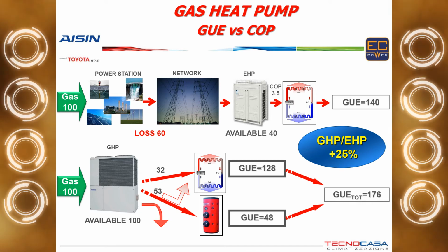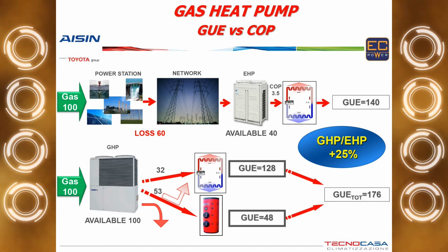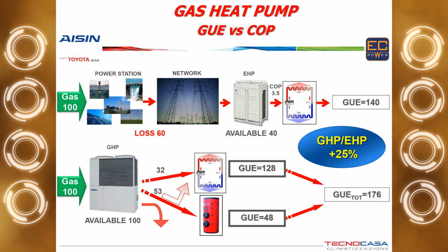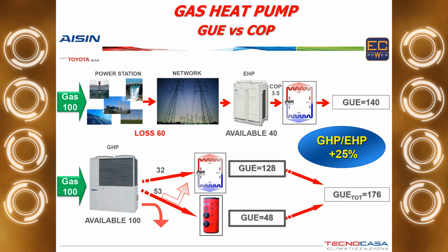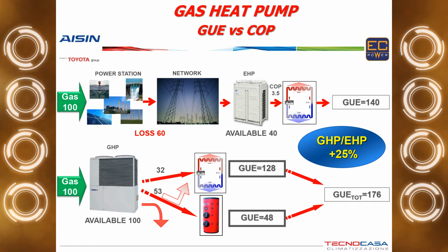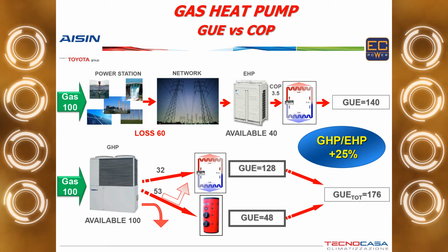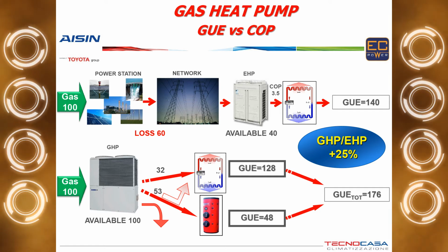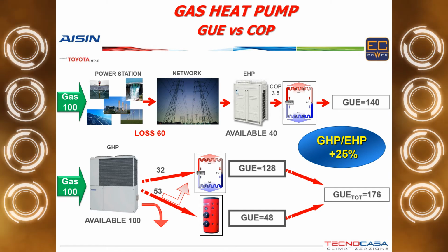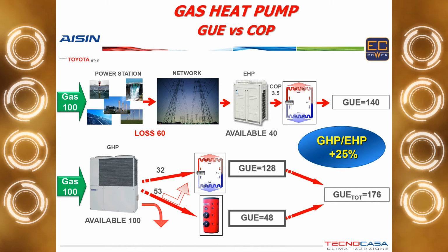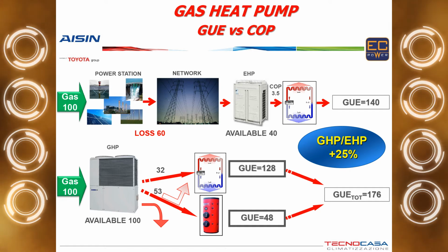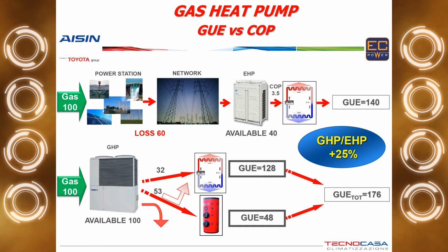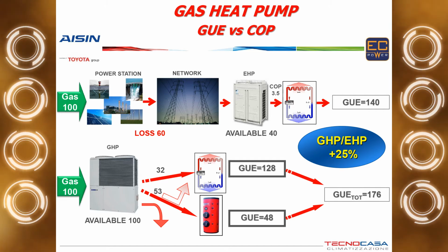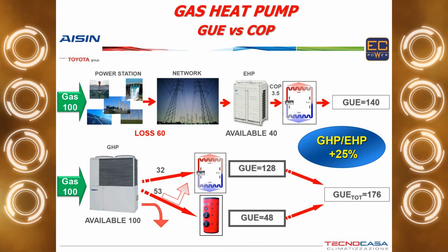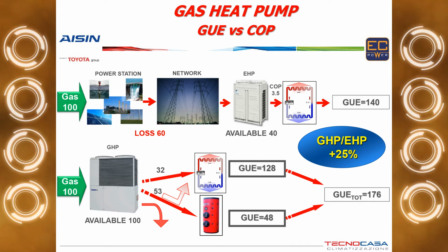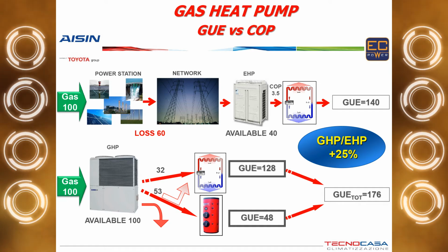When you put this into the heat pump and you use the heat pump, what you have is a gas utilization efficiency of 140. If you do the same with the gas heat pump, there is no conversion between gas and electricity. So you are taking out the production and the distribution losses of the grid. So if you take only into account the refrigerant system, what you have is a gas utilization efficiency of 128. But then we have the heat recovery, which adds 48 extra. In the end, you can reach 176, which means 25% higher performances compared to the electric heat pump. And also you have to consider that the performance stays when the outside temperature drops, because we are using the engine coolant for the evaporation.